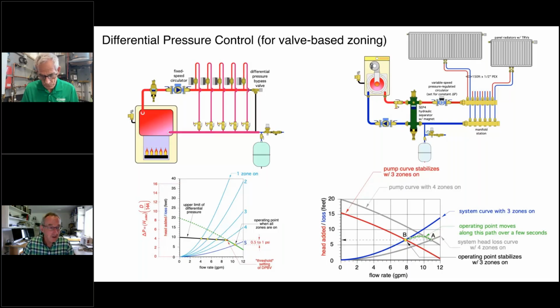Again, if you're dealing with a fixed speed circulator and zone valves, two things. Put in a differential bypass valve, first of all, and then you also want to select a circulator with a relatively flat pump curve. What you don't want to do is put a circulator with a steep pump curve. That's going to just exacerbate the change in differential pressure as the zone valves open and close.